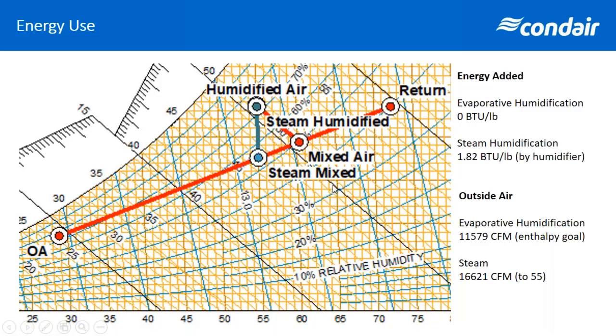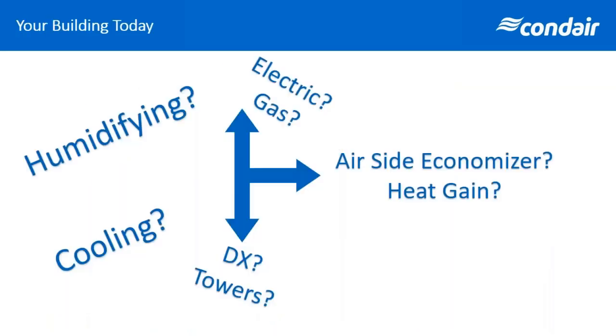So if you are somebody who likes psychrometric charts, when we boil water and we go straight up in that teal color there, we're adding energy to the system. For an evaporative system, we are just taking a different mixed air point or a warmer air coming in and putting some water towards it, and therefore ending up at the same point but using significantly less energy. So if you wanted to know the mechanics, there's a very brief overview of the mechanics.